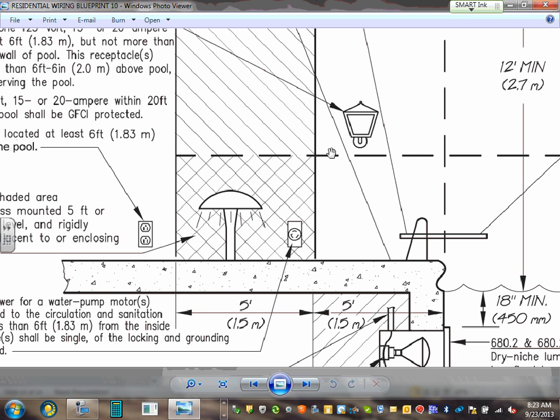Switch is not closer than 5 feet. When you put your switch around the swimming pool, make sure it's not closer than 5 feet. Otherwise, you have to have a listed switch, a listed low voltage switch. Any comments, guys? Any questions? So that's basically it for your swimming pool. Let me just go very quick, guys. For swimming pool, I don't know if we forgot any.